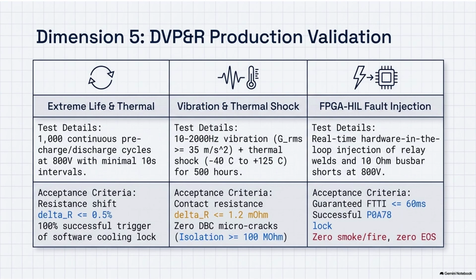And the first torture test the document outlines is the extreme repetition test. This addresses the impatient driver scenario head-on. They hook the unit up to a massive dynamic test bench pushing a full 800 volts of raw direct current, and they force the software to execute 1,000 continuous pre-charge and discharge cycles. And the most critical parameter of that test is the time gap between the cycles. They set the interval to the absolute minimum safety threshold permitted by the software, which the document notes is a mere 10 seconds.